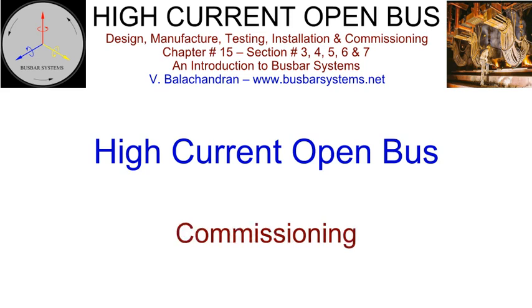Commissioning. Commissioning of DC open busbars does not pose a challenge since the voltage levels are very low. It is necessary to monitor the temperature of the conductor joints with an infrared probe for hot spots. Apart from the hot spots on the conductor, open AC busbars do have to reckon with eddy current losses induced in the metallic structures in the neighborhood. Additionally, hysteresis losses will be induced in the ferrous metallic structures.